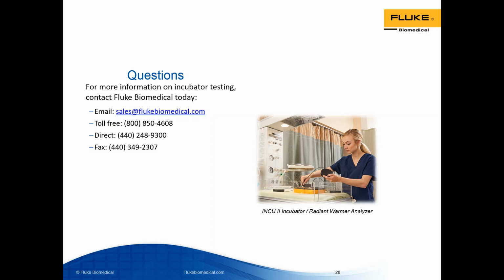Okay, here's the next one. Does the Fluke test equipment meet or exceed testing requirements for all incubators available for purchase in the U.S.? Yes, it does, because all incubators in the U.S. are manufactured by OEMs that are regulated by the FDA, and remember that all ties back to the standards. So for incubators, transport incubators, and radiant warmers, the IEC 601 standards are 2-19, excuse me, 2-20, and 2-21 respectively. So all of Fluke's devices, especially those, like the INCU II I've got a picture of on the screen now, that are specific to incubator radiant warmers, are compliant with all the global standards, yes.